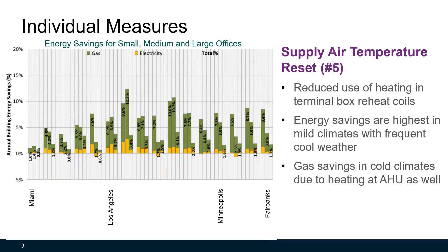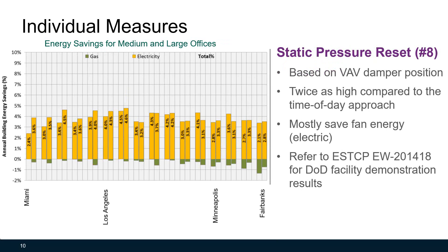The next measure is supply air temperature reset. The air handling unit supply air temperature reset reduces the use of heating in terminal box reheat coils, and the energy savings are highest in mild climates with frequent cool weather such as Los Angeles or San Francisco. The energy savings for the static pressure reset strategy is mostly on electricity — this strategy primarily saves fan energy.